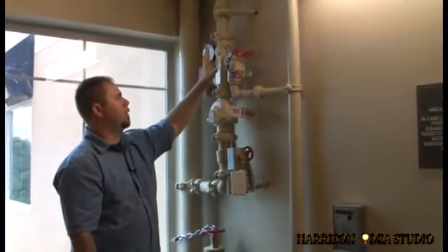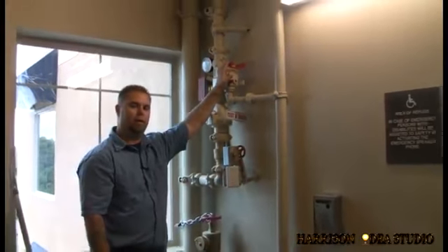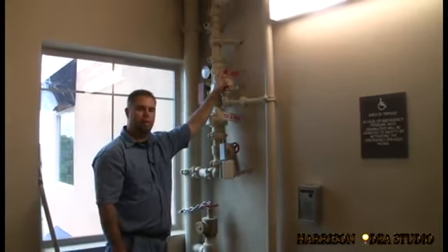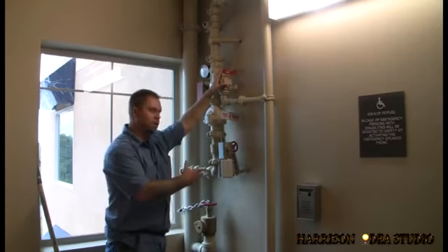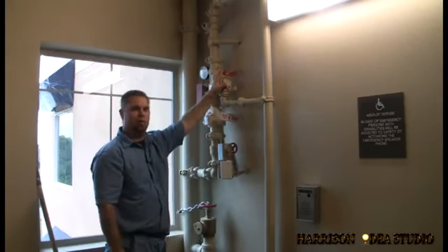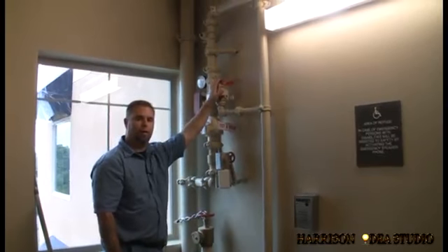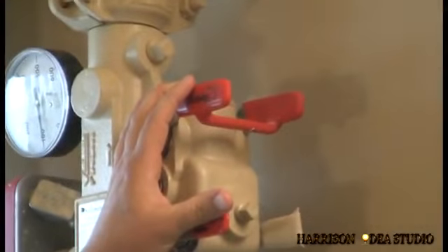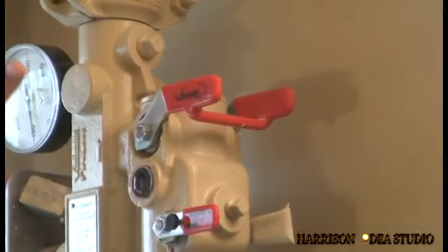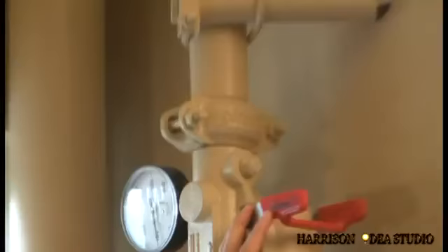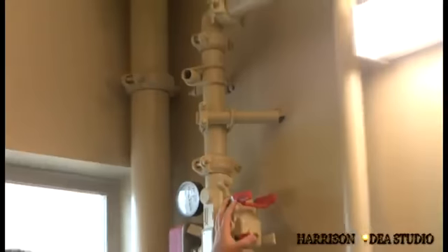And here is your main drain, test and drain. Once we shut the system down at this floor, we will use this valve to drain it down and do our service or whatever we need to do. And this is basically your riser and your main that feeds this entire floor, the sprinkler system on this floor.